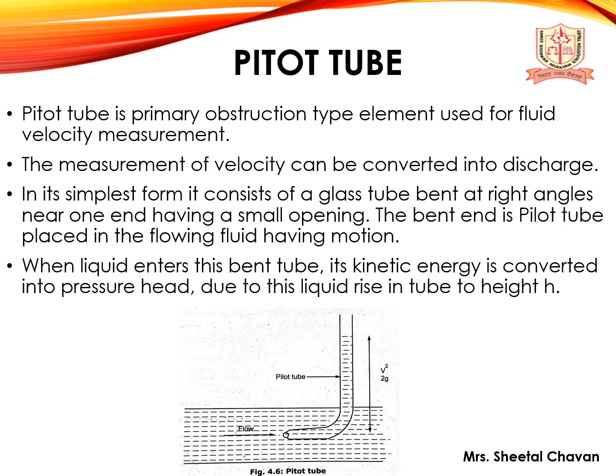The pitot tube is a primary obstruction-type element used for fluid velocity measurement. The measured velocity can be converted into discharge. In its simplest form, it consists of a glass tube bent at a right angle near one end with a small opening. The bent end is placed in the flowing fluid, converting the liquid's kinetic energy into pressure head, causing the liquid to rise in the tube to height h. The flow velocity is given by V = √(2gh).